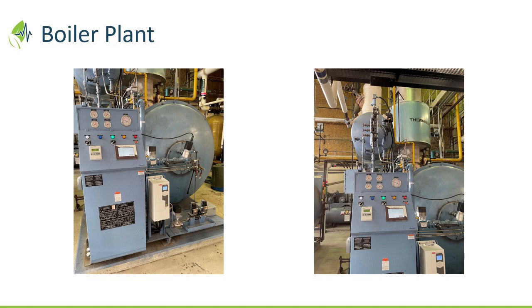So you never want positive pressure on that boiler unless you're running a power burner on some of your newer condensing boilers. But even then, everything's designed for a slight negative. So if everything's designed for a slight negative and the summer is the worst case, what's the winter draft looking like on anything, right? It's significant. So keep that in mind on any of your projects.